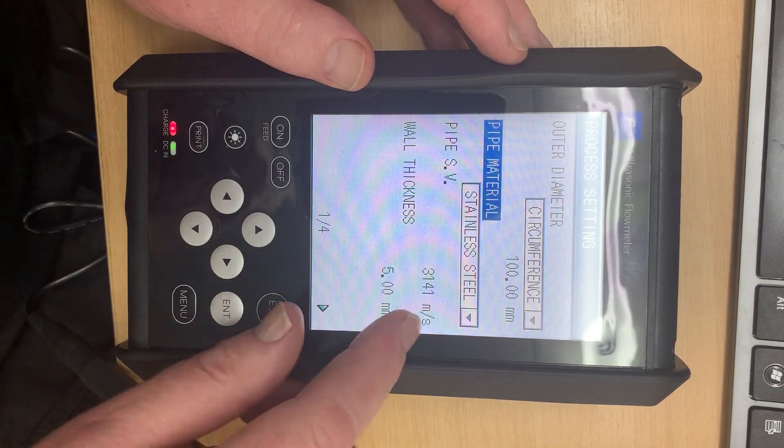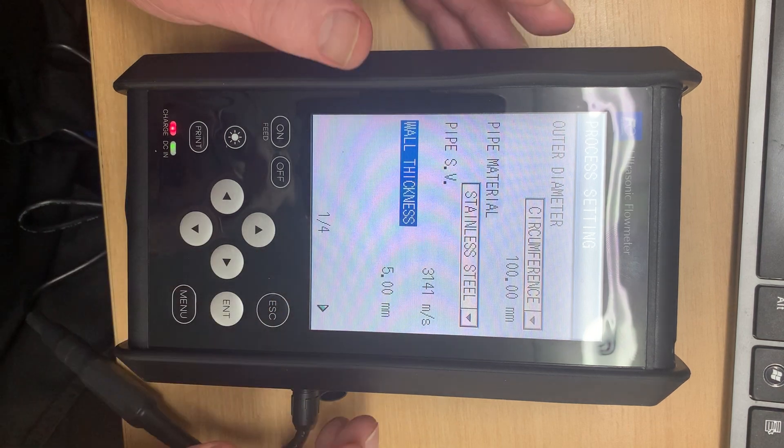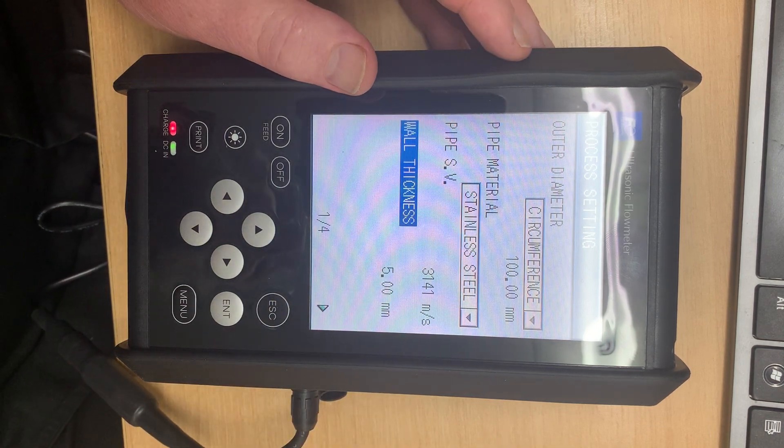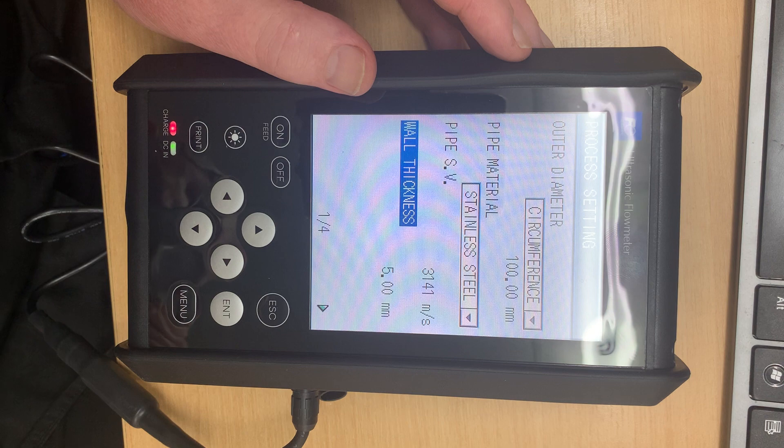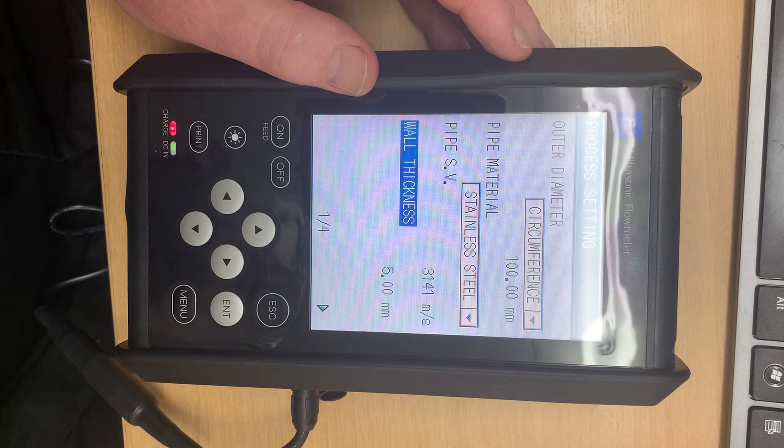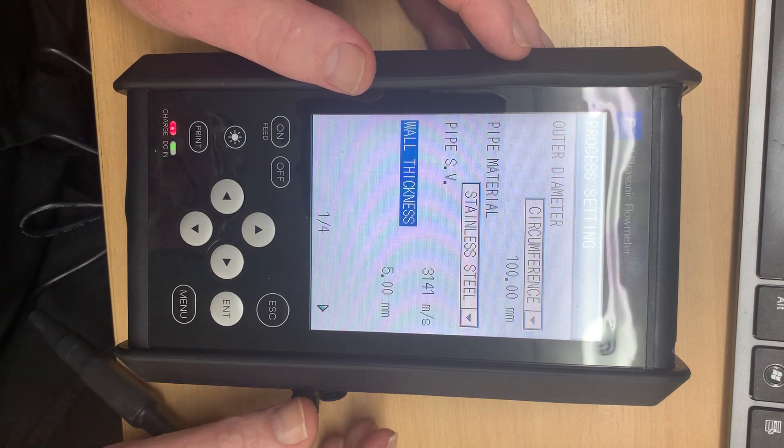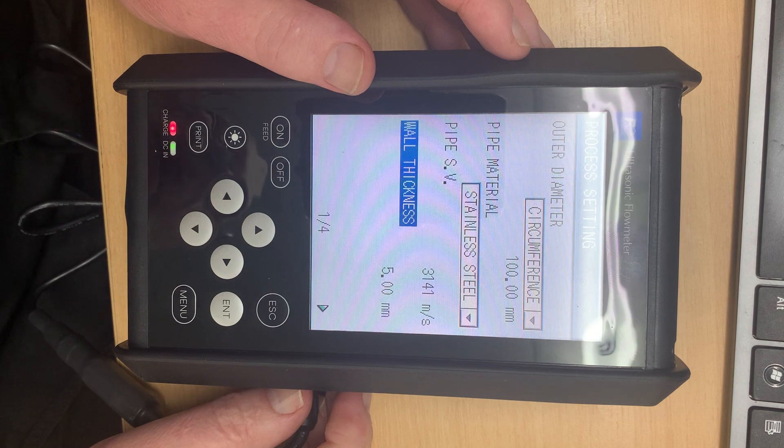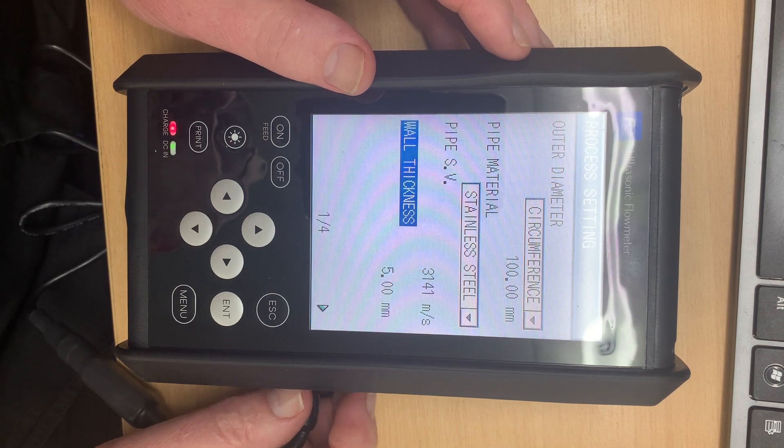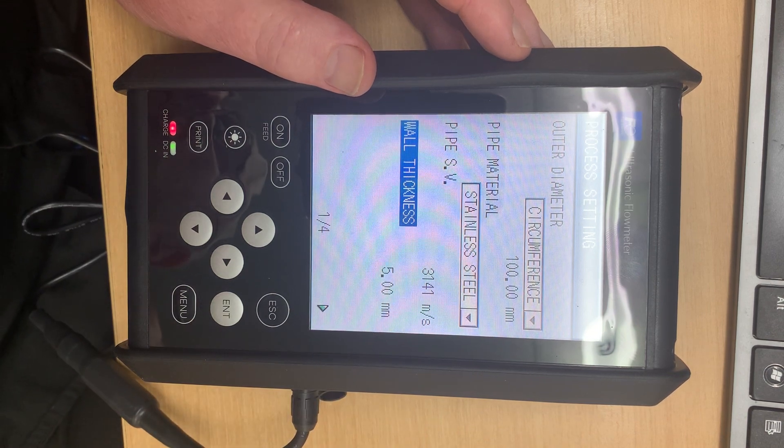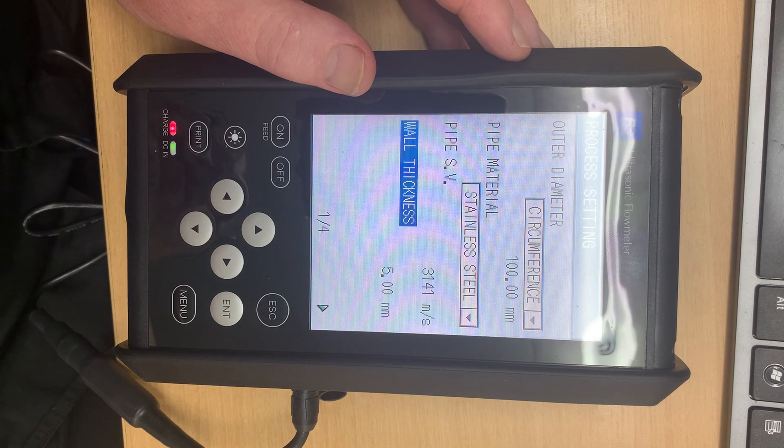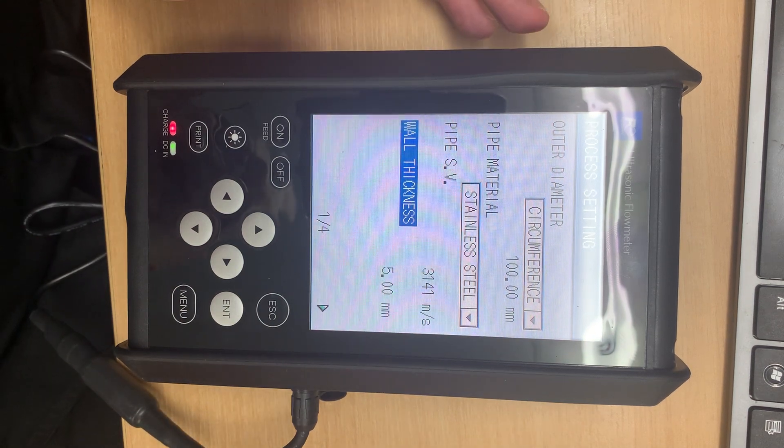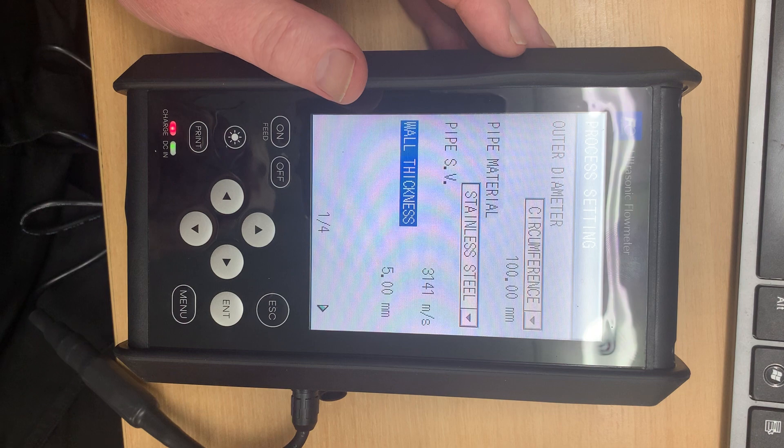Now we put in the wall thickness. That's an important measurement because as you've correctly pointed out it is a time of flight machine. So the pipe wall thickness is important. I can't remember whether I put on your quote a thickness gauge or not, but most people when they buy one of these buy a $900 thickness gauge to measure the wall thickness.